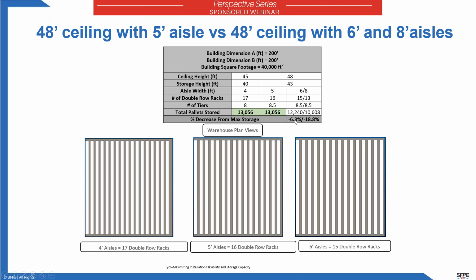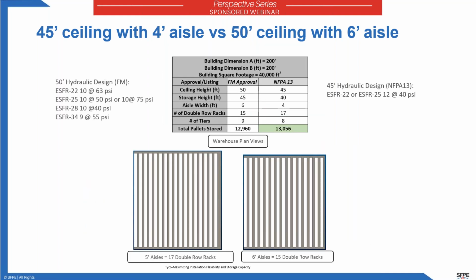So just changing the aisle width allowance has a significant impact on how much storage, how many racks you can put into a warehouse, and how much storage is allowed. So let's look at the 50-foot ceiling approval. As I noted, FM now has ESFR approvals with the 50-foot ceiling, and all of those approvals are with a 6-foot aisle. So looking at the FM approval with the 50-foot ceiling and 45 feet of storage and a 6-foot aisle, you have just under about 13,000 pallets that can be stored.